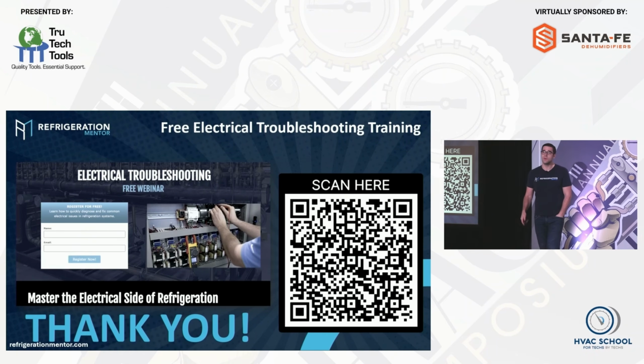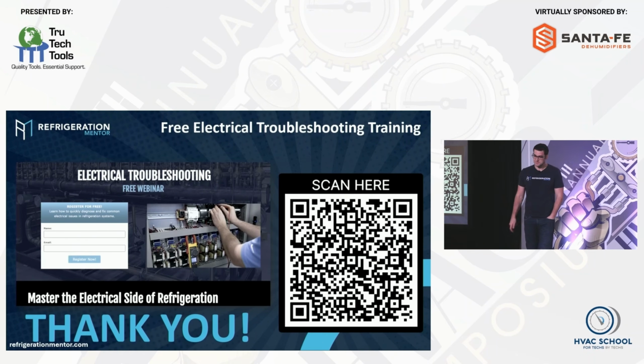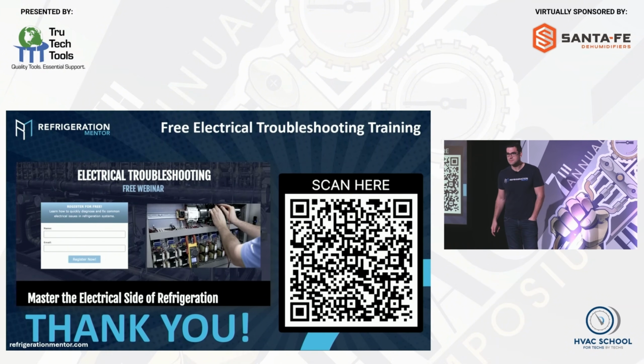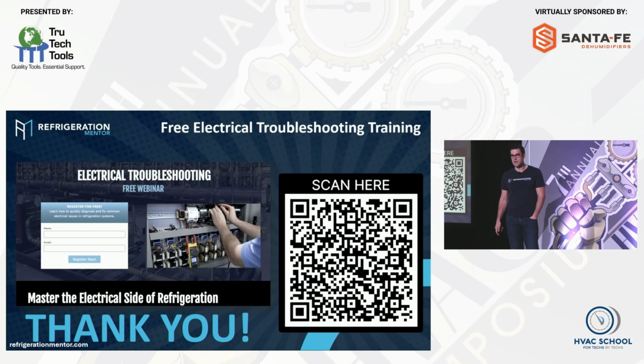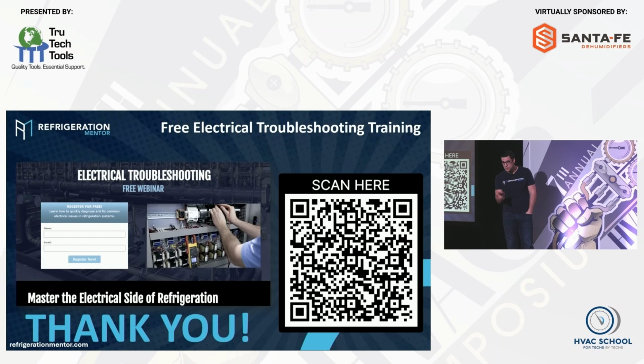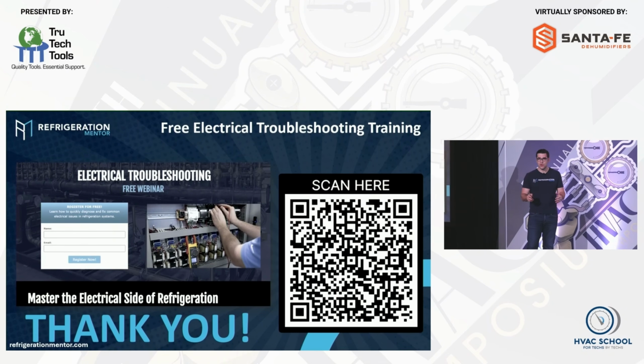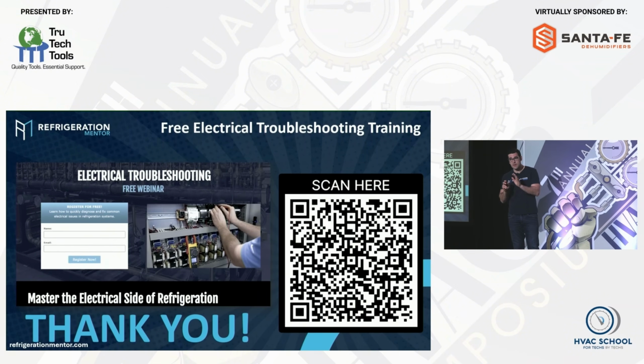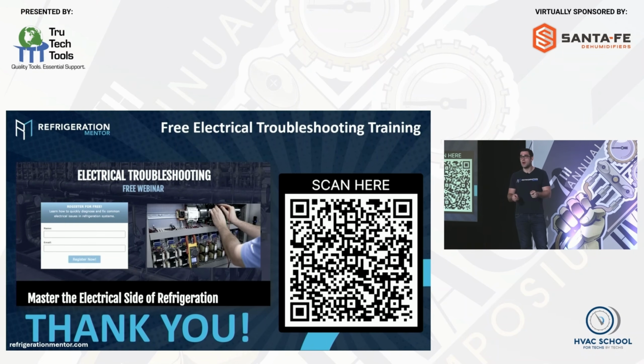Intermittent failures. What do you do for intermittent failures? Basically repeat the process until I can get it to fail. Yeah. One of the biggest things I used to do, which was a mistake, is I used to reset. When a system tripped, I used to reset the system. Don't do that. Get your meter out and try to find out where it is. If it's an intermittent failure, those can be hard, because it could be a wire that only trips when you open a door and there's a short, and the only time it happens is when you open the door. Okay? And sometimes it does take longer. Sometimes you have to change a certain part to check that.